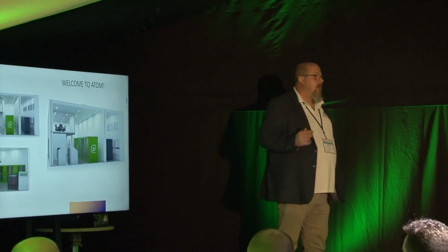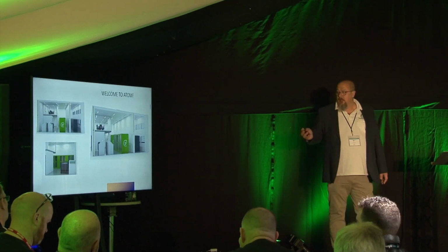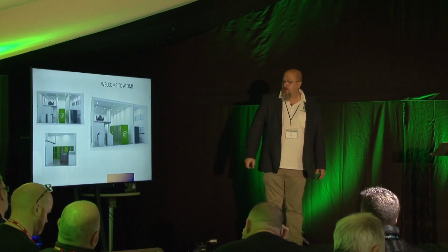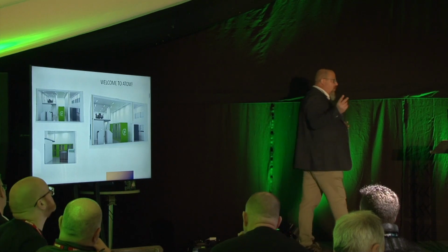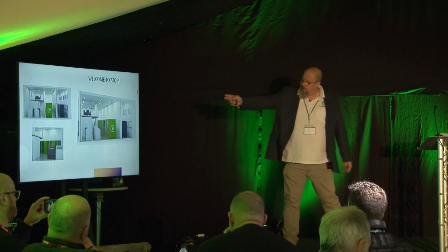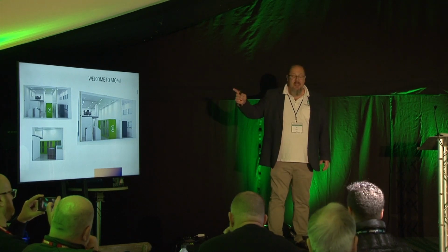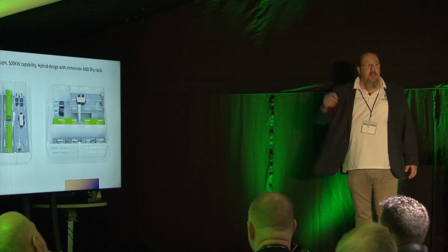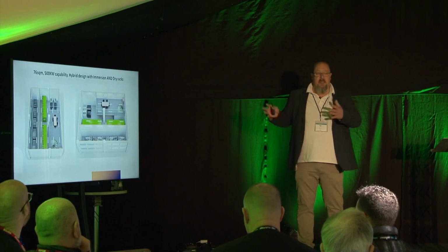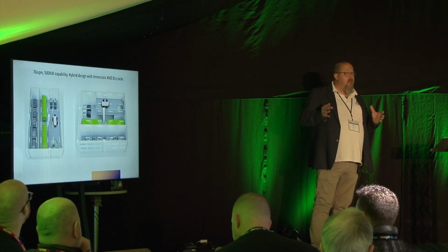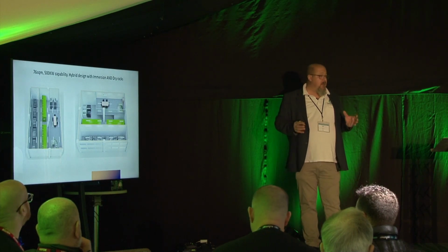This is one which we actually worked on with our partners at Sudlows, Submer, Intel. Everybody's been involved in this design. And what it is, 76 square meters. You will see it's colored. The green racks are self-contained dry racks. These little triangular ones and the little black ones on the bottom left, those are the immersion baths. They're the smaller versions of what we have here. These huge black tall things are the cooling systems. They're inside the building. We can actually modularly swap these out. We can take out 100 kilowatts of dry rack, and in that footprint, we can put 200 to 300 kilowatts of immersion cooling. So that's my bit.